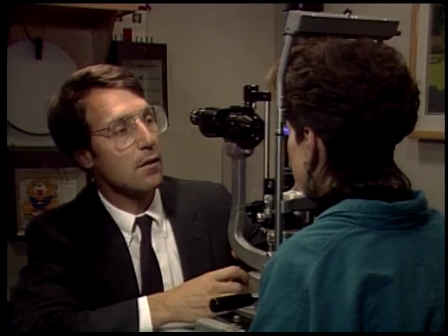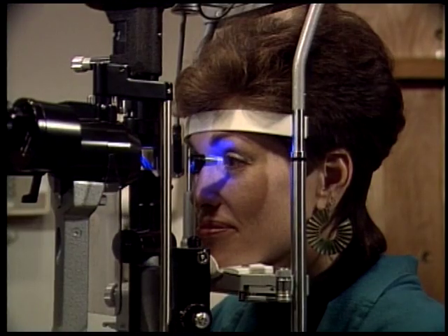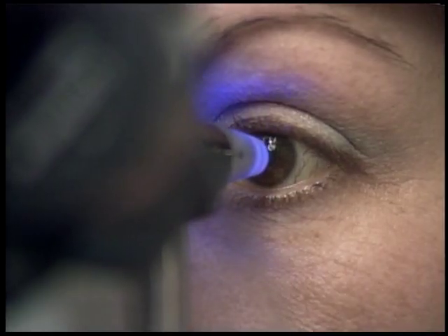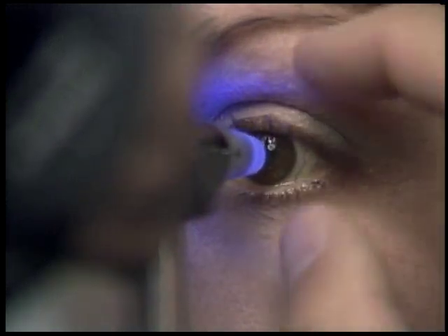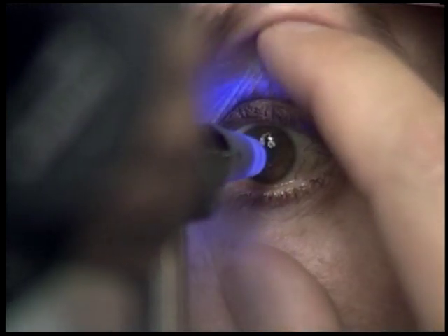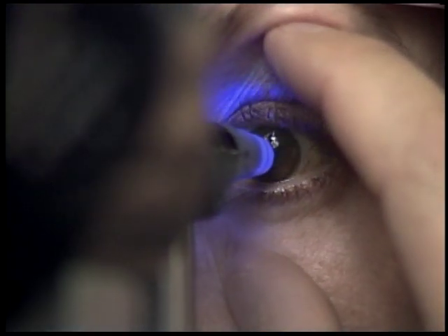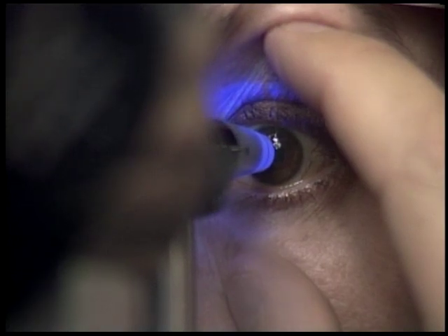The eye should fixate on a target away from the tonometer. It is important that patients not hold their breath. Rather, they should try to be as relaxed as possible. The lid should not touch the tonometer.